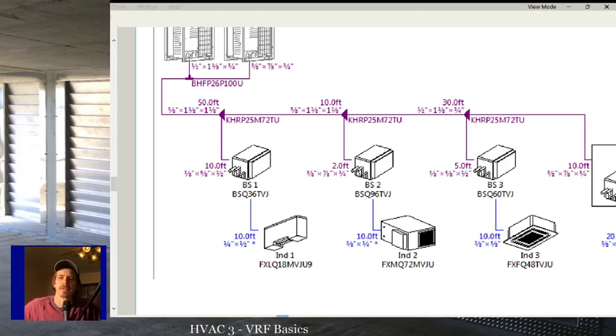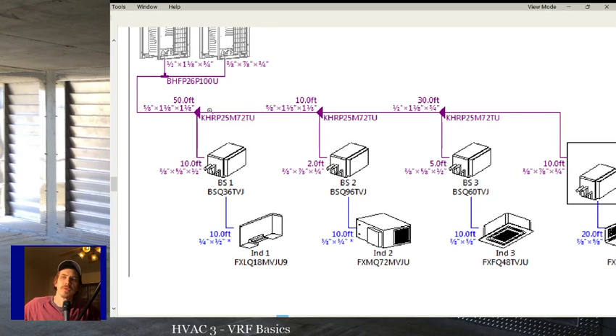So, if you're installing this system and it's not 50 feet from the outdoor unit to the first unit, it's 80 feet, then you need to report that information back before you install the line set and make sure that's going to work. And if it's actually 20 feet from that Y to this Y, then you need to report that back before you bother piping it. So you need to have a good layout of what you're going to do before you do it, and report that information back to the engineer so they can make any necessary changes before you do it. So it's really important to lay everything out, have a path, put up all your hangers and stuff first, and then after you've got a good plan, go and do it. A change of a few feet here and there usually won't make a difference, but it might. So you need to know.